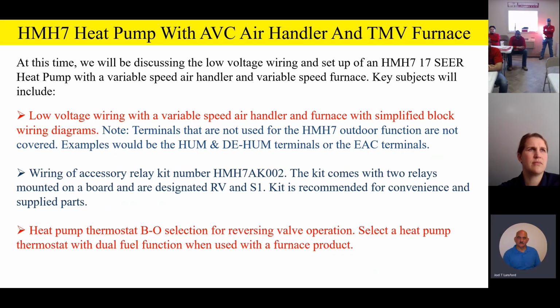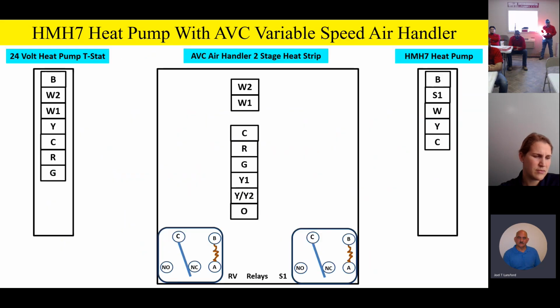Now, please remember, anything variable speed, you've got to have the 002 kit, except our new variable speed air handler does not require it, because the board itself can be configured on the air handler for this S1 input. But if it's an older AVC air handler or any of the variable speed furnaces, you're going to have this 002 kit. Remember, if you're going on a furnace, you've got to have that dual fuel operation. But let's take a look at an air handler configuration. This is a variable speed air handler, the older style, and you're going to notice it's got 2 relays on there. The 002 kit has 2 relays. Those relays are designated RV and S1. So let's take a look and see how this is wired up.